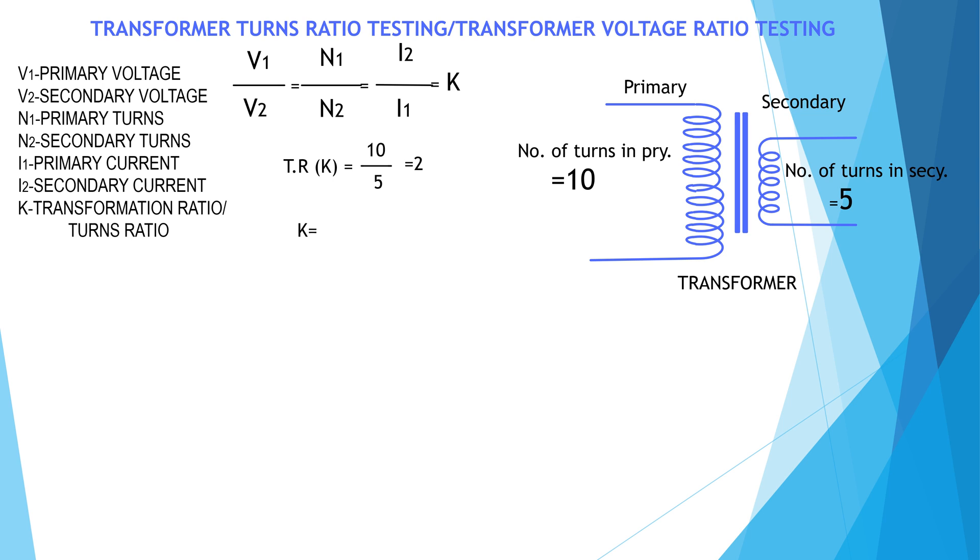So voltage ratio is equal to 2. The voltage ratio is equal to phase voltage V1 by phase voltage V2 which is equal to 2. We have to test the voltage ratio or turns ratio at each tap as each tap has different turns ratio.